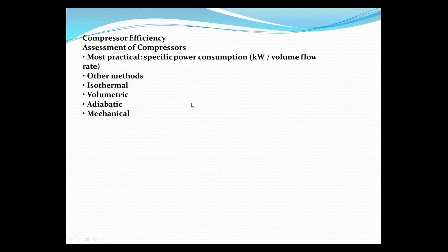Clear? So the capacity of the compressor, as I told you, FAD is the term used to designate the capacity of the compressor. FAD is nothing but the full rated volume flow of air or gas which is compressed and delivered at the conditions of temperature, total pressure, and composition prevailing at the compressor inlet. This compressor inlet is in bold. So in short, the compressor gives you the actual flow rate at the atmospheric condition at any specific location, in Nasik, or suppose you install it in Ladakh. So for FAD, you have to convert your delivered airflow rate to the inlet condition. But remember that FAD is not at the ideal or STP condition. FAD is not calculated at STP. FAD is purely calculated at the atmospheric condition of that particular specific location.